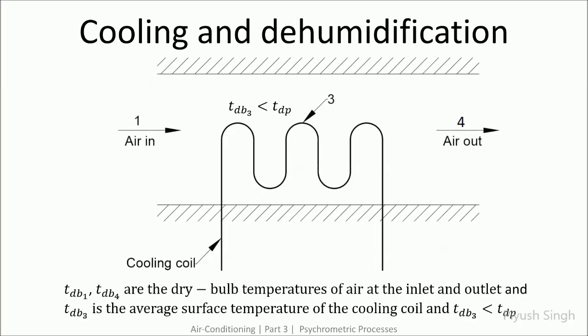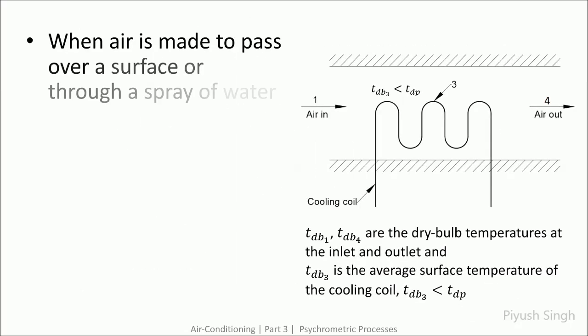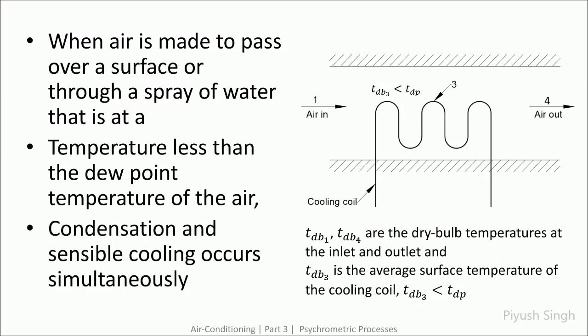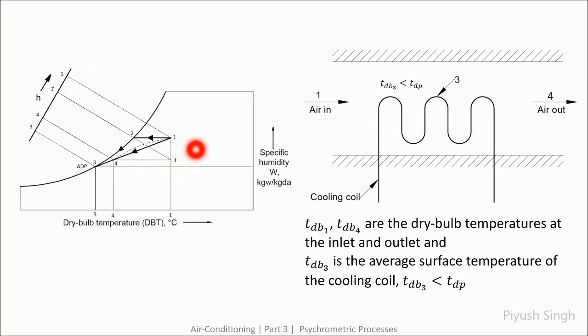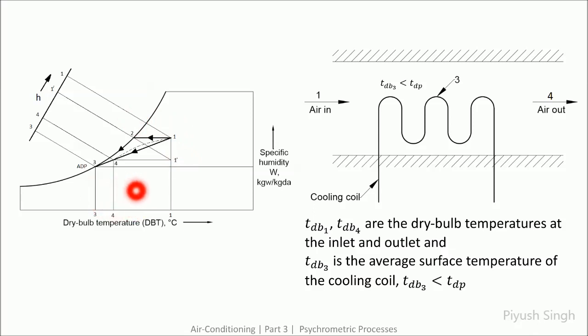The next process is cooling and dehumidification. Here, the coil temperature must be lower than the dew point temperature of the incoming air. When the air passes over this surface, condensation and sensible cooling occur simultaneously. On the psychrometric chart, this process is represented by a line connecting the apparatus dew point and the initial condition, with the final condition lying between these two points. In actual practice this may not be a straight line, but for simplicity of calculations it is assumed to be a straight line.